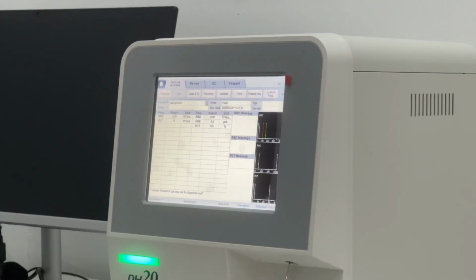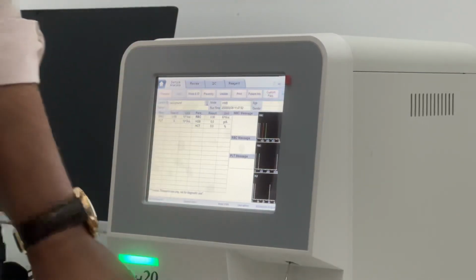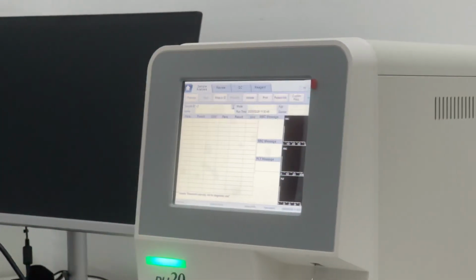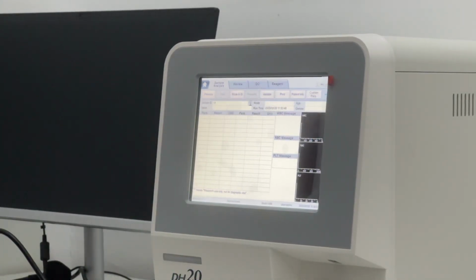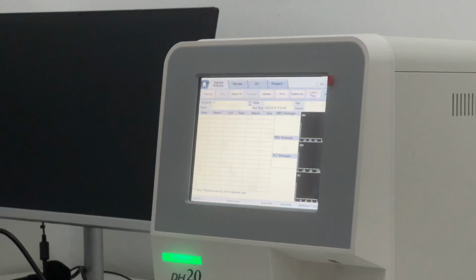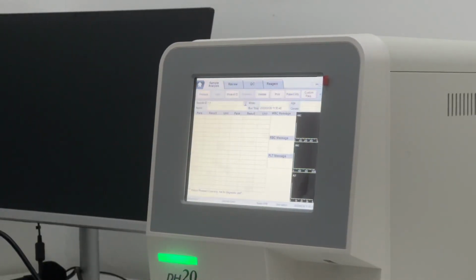When they put it as a default setting, that means everything starts from zero. So whenever the machine is on, we will do the blank count. Blank count means without sample. There's no sample. This is called the aspirator. We will press this one. Now consider the machine is running, analyzing without sample in the default setting. The machine knows that there is no sample. By right, if no sample, then the result everything must be zero. That's what they're trying to explain to us. So the result must be zero and stars. Some of the results show stars, but it's nothing but zero. The value is zero. So we will wait for the result to come out.